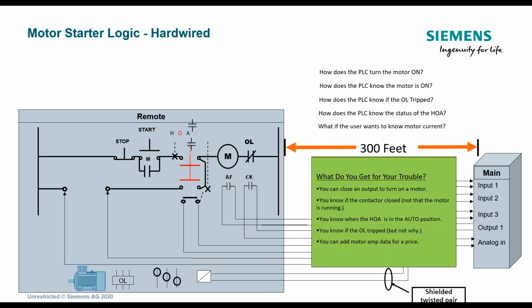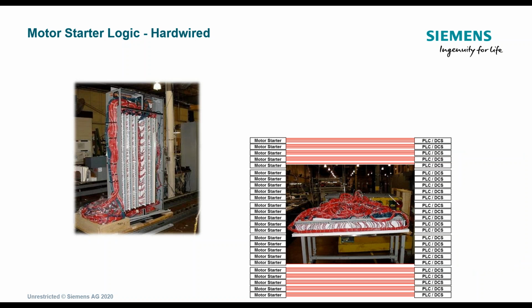But what do you get for it? What trouble do you get into? You can close an output to turn on a motor. The contactor could close, but the motor's not running. Your HOAs may not be working. Some mechanical contacts have gone bad. You know if the overload is tripped or not, and then you can add motor amperage data for a price: a big analog card, and then that twisted pair. But understand that these contactors add another mechanical property where they have some intermittency, or the contactors can go bad in the field.